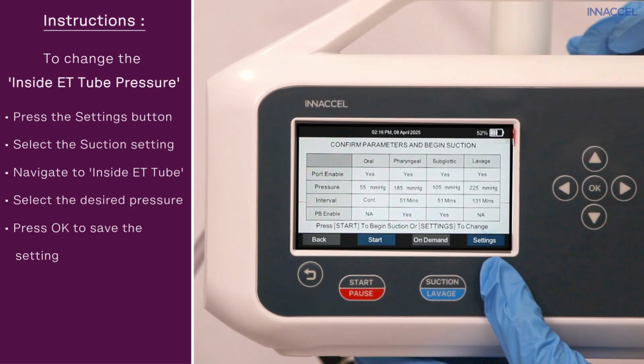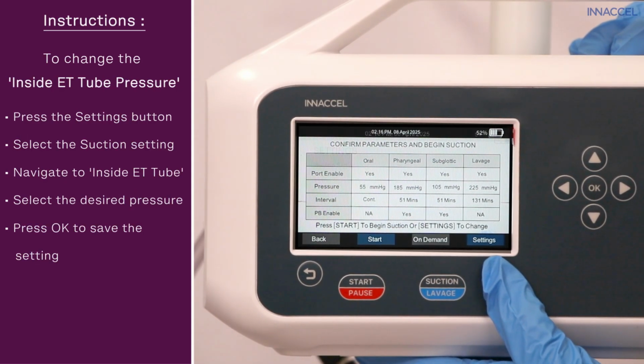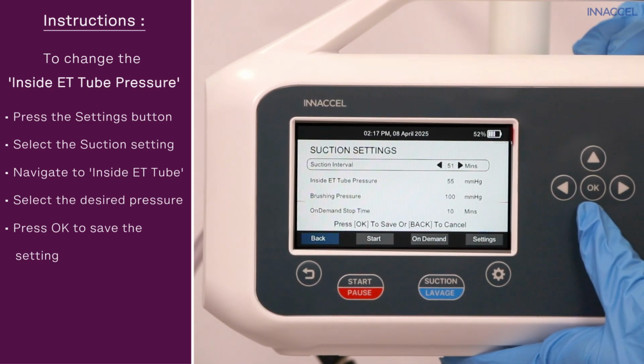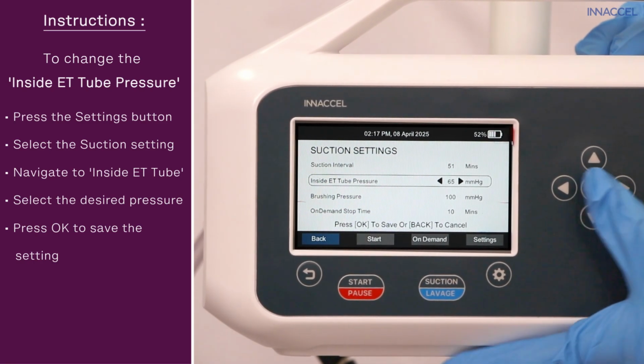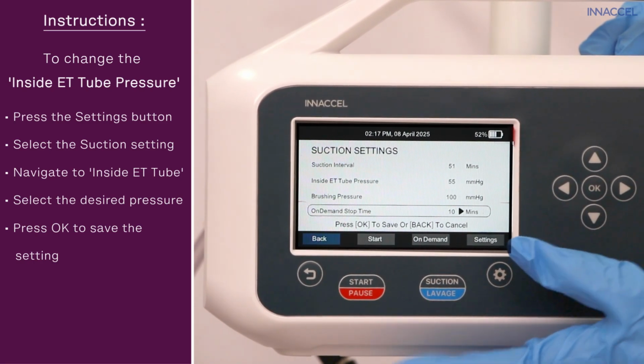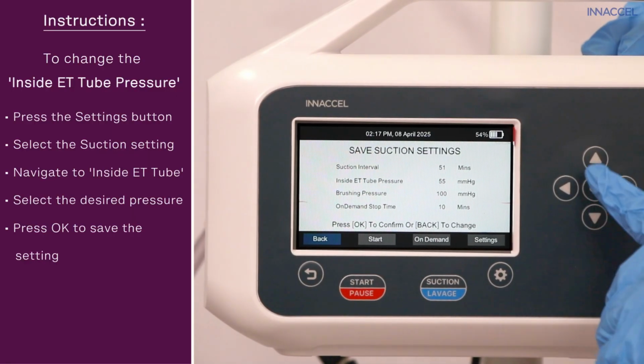To change the inside ET tube pressure, press Settings button and select Suction Settings. Now navigate to the inside ET tube pressure, and select the desired pressure. Now press the OK button to save the settings.